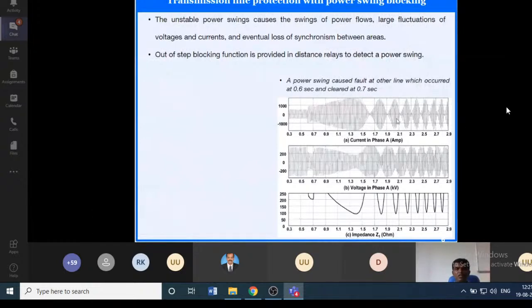How is it? There is a fault at some other line which occurred at 0.6 and cleared at 0.7. The fault is cleared, but even after the fault clears, the power oscillation exists till this period. This will be called power swing. This is the current waveform, this is the voltage waveform. You can see that the current and voltage waveforms are oscillating severely.